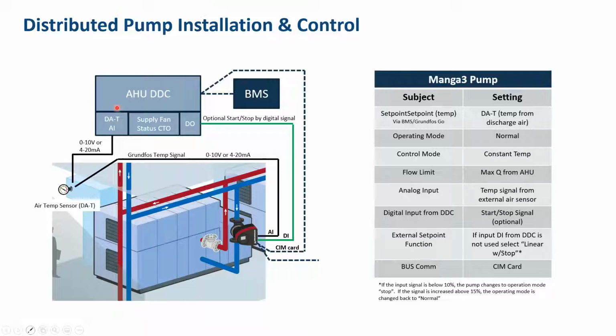So if we have the control capability there and we want to feed that temperature sensor into the DDC, then we would take our speed signal from the DDC, and we would also have the option to do the same thing through the BMS system. We would take an optional start-stop from the DDC, so we knew when to be on or off with that distributed pump. But it really is as simple as that. Those would be the three options, and those would be in order of preference for Grundfos anyway.